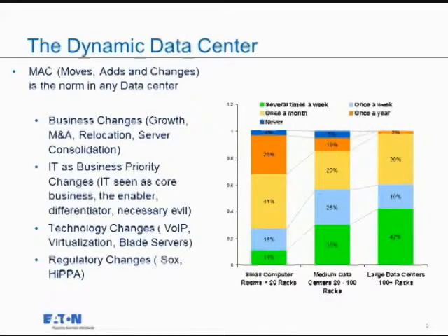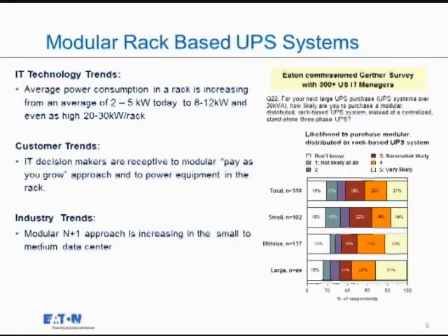We also asked the same kind of group, how likely are you to purchase a modular approach to this? Gentlemen, in the last piece we were talking, and we got off onto a little bit of a tangent about a large data center: rather than putting in a single large UPS, it might be more beneficial to put in 10 small UPSs, one at the end of each row, to get that flexibility. Now I can turn off rows or turn them on and move them around. So this modular approach, and the numbers kind of justify it.